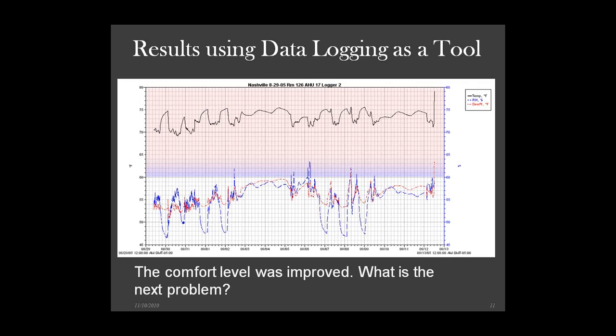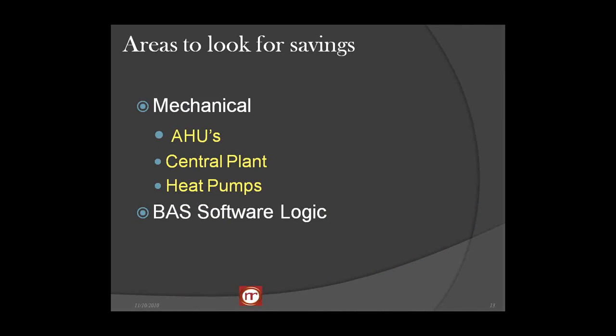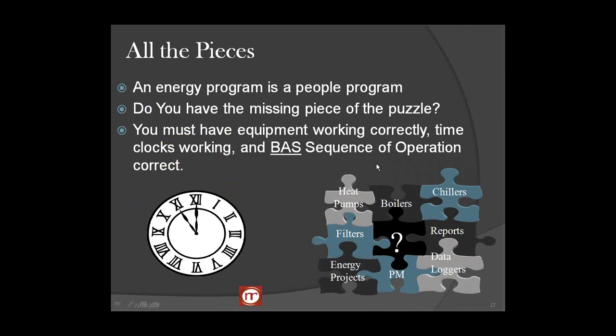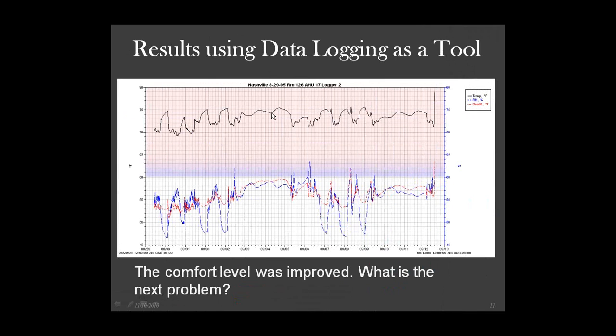And another thing to point out here, we did a great job on the comfort level. We'll look at the next problem down here. What do you see? If you know anything about a building, you know that you have night setbacks, unoccupied times and unoccupied temperatures. Well, our unoccupied temperatures in the summer are 85 degrees. Notice that during the weekend, right here, we're hitting about 75 degrees. Well, we did a great job improving the comfort level, but let me go back. If I go a little bit further on problem number 2, I need to get this up to the 80 to 85 degrees, and things would do a lot better for us and save a lot more energy.